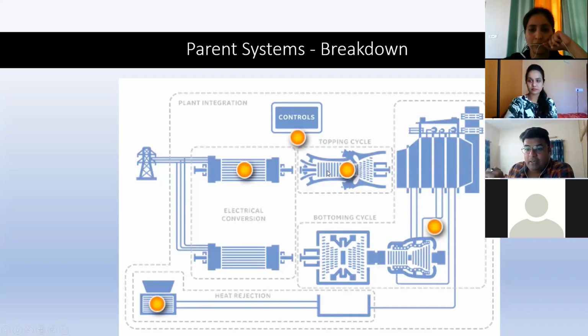Topping cycle is nothing but the gas turbine cycle, or quick response turbines, which don't need a lot of energy the first time to start operating. So you have topping cycles as gas turbines in a power plant, in a combined cycle power plant, and the exhaust of the gas turbine goes to the HRSG, which is part of your bottoming cycle.